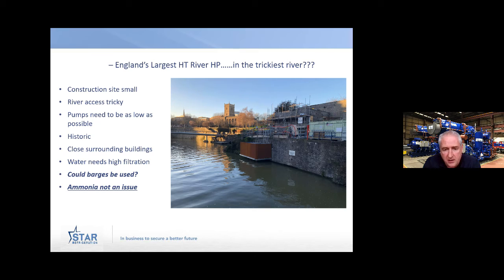But an interesting appraisal of this, the working fluid is really important. We're working through as an industry from CFCs, which everybody knows is now banned. There have been subsequent working fluids used. The only working fluid used consistently since 1880 is ammonia, and that's for very good reason. One, it's not environmentally damaging the ozone layer or creating global warming, but it's also the best efficiency, and that is the number that will always stand out in the spreadsheet - how many units of heat can I get for my unit of electricity.